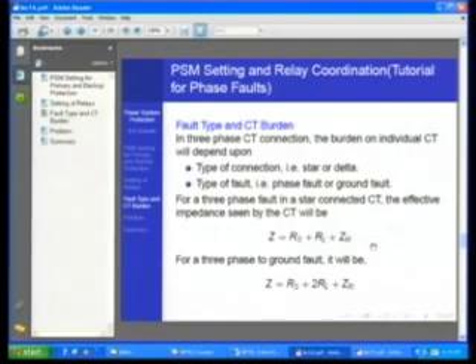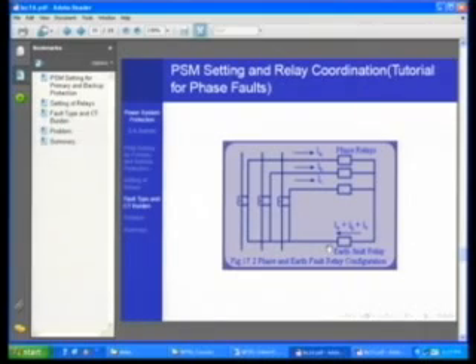Okay, just a small point here. CTs in a legacy system will, for a phase fault, see RS plus RL plus ZR as the relay impedance, in a legacy system, that means where you have 3 phase relays, 1 earth fault relay and so on. For an earth fault, the current will flow back through the lead wire, because with a phase relay, IA plus IB plus IC becomes 0. So after that nothing flows through the ground wire back in some sense. There is no return circuit required. But this requires a return circuit for earth fault. So therefore the CT sees different impedances when there is an earth fault and when there is a phase fault in a legacy system. And the earth fault system sees more impedance than the phase fault systems. There are further issues of star delta connections and so on, but I am not going into details of that.